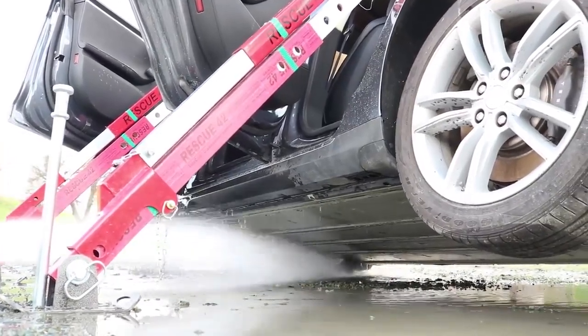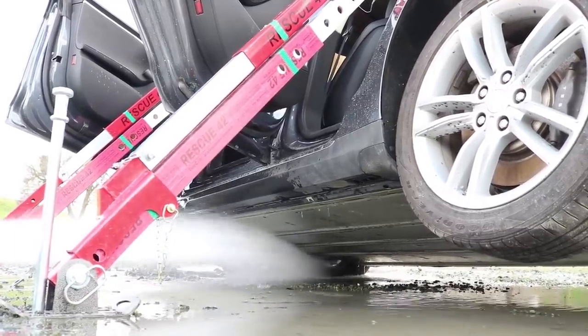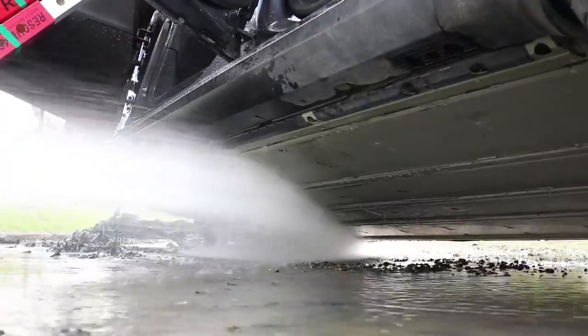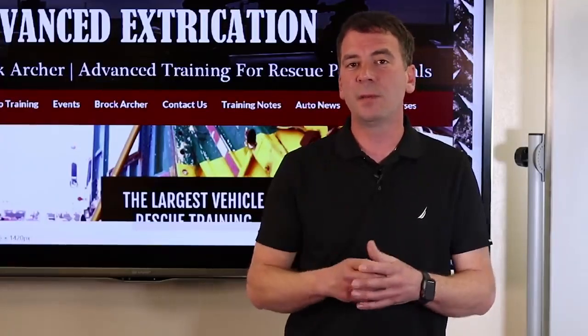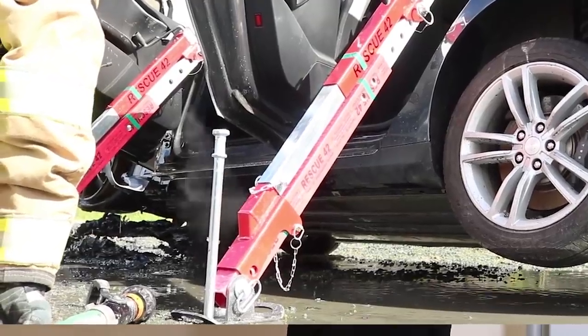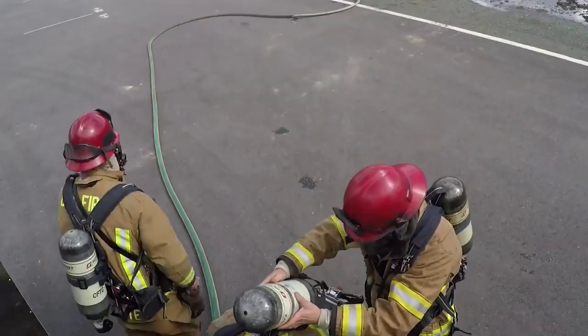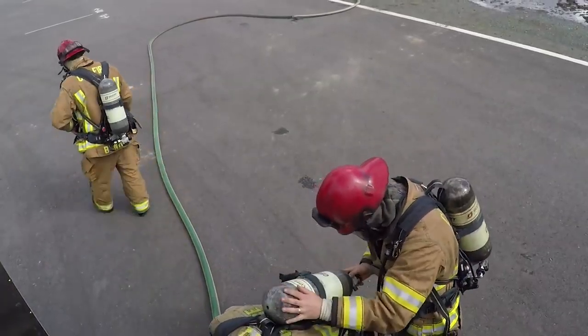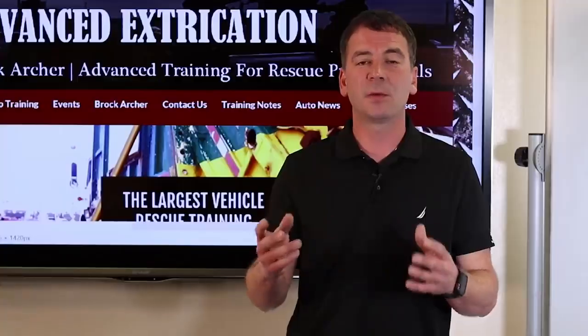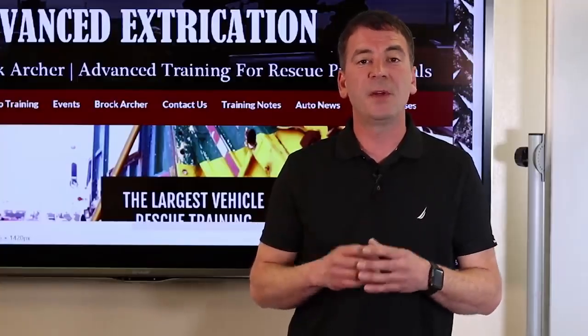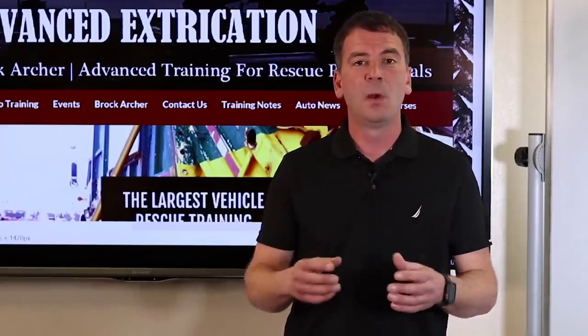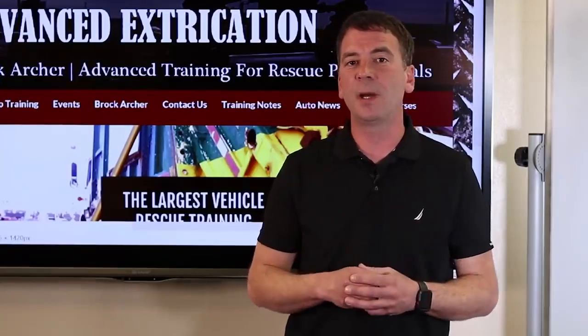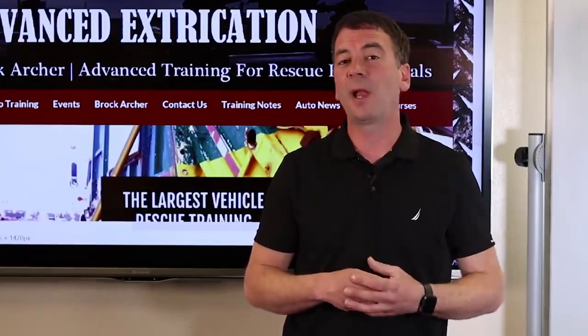Once we see visually that the battery has been cooled, either by no more smoke or steam coming off the battery, or a clean reading with our thermal imaging camera, we can stop our cooling efforts. At this point, monitoring the battery for smoke or steam, or with the thermal imaging camera, for 45 minutes before we release the vehicle to second responders is appropriate. If at any point during our waiting period we see any indication of heat buildup, water should be applied to the battery again.